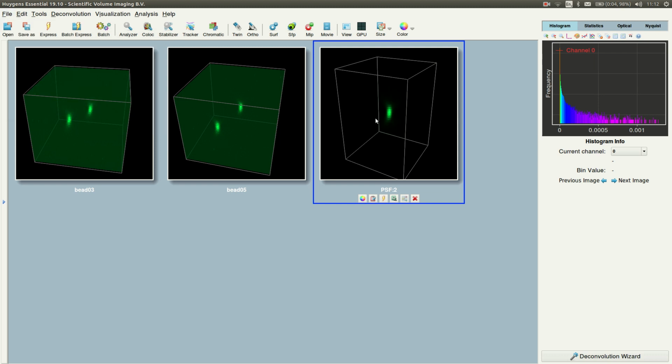So if you do multi-channel imaging, then you would want to use beads that are also imaged in multi-channels, so we would recommend Invitrogen TetraSpeck beads for that, and these can be excited with four different excitation colors in the spectra of the most widely used fluorophores. So this is very useful to directly image four channel point spread functions, and it has the simultaneous advantage as well that you can also do chromatic aberration estimation afterwards. So yeah, that's it.